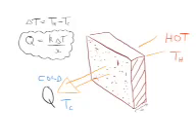Now, typically, the best performing natural insulators have thermal conductivities about twice that. And what that means is that if you want to get the same rate of heat transfer across a wall with natural insulation for a given temperature difference across that wall, then you're going to need twice the thickness of wall, compared to a wall where the insulation is this PUR, PIR synthetic stuff with a thermal conductivity of 0.02.